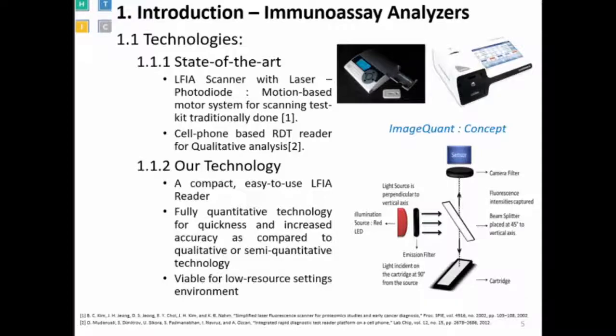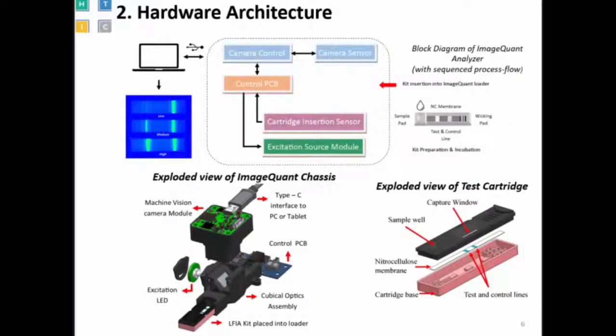The test line intensity is measured with reference to the control line. Regarding the hardware architecture, our system is connected to a Windows-based laptop, computer, or tablet, where the main software runs for signal processing and analysis. The displayed hardware consists mainly of an imaging camera, along with control elements including a sensor switch for detecting cartridge insertion and an excitation module for exciting light intensity on the cartridge for fluorescence measurement.